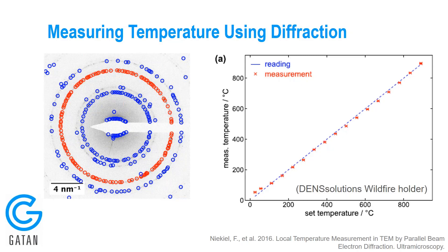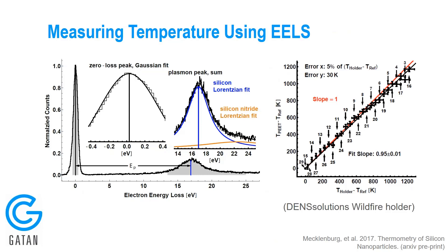They found that the temperature measured using diffraction matched the temperature given by the DENS Solutions holder to within 5%, as DENS Solutions claims. The final example of measuring temperature inside the microscope returns to EELS. This group at USC, led by Matt Mecklenburg, is using the plasmon peak energy to measure the temperature inside the microscope — measuring the plasmon peak by fitting a function to the data. They're able to measure the temperature fairly precisely, and again find that the difference between the measured temperature and the nominal temperature given by the DENS Solutions holder is within 5%.